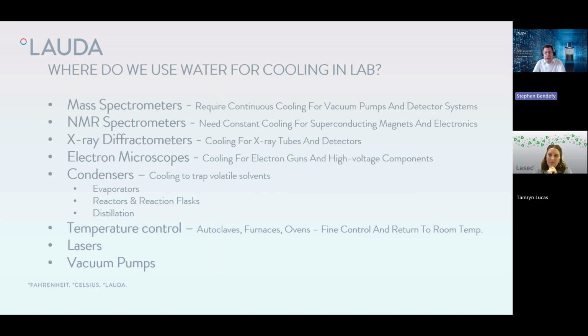So considering water usage, where do we use water for cooling in the laboratory? Well, there are a number of different applications, including analytical equipment such as mass spectrometers. These require continuous cooling for vacuum pumps and detector systems, as do NMR spectrophotometers, X-ray diffractometers, and electron microscopes. We recognize that maybe you don't have any of these for yourself directly, but perhaps in your company as a whole this equipment exists and consumes water constantly, or perhaps it's already connected to some kind of water cooling system.